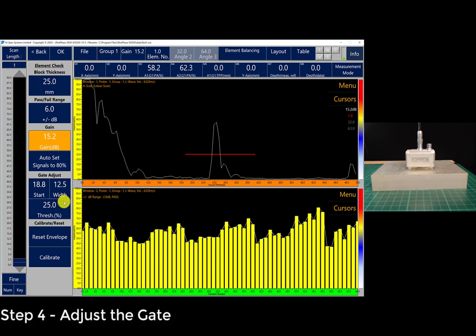Step four would be to adjust the gate so it encompasses the back wall of the test block. You can see in the top A-scan window that is fine.